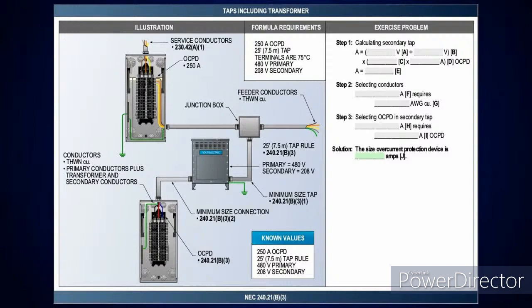All right. Absolutely. Now this one, you've got an upstream 250 amp overcurrent device that's given. In this case, we've got a 480 volt primary, 208 volt secondary. So you're going to have to get the ratio of that. Then I'm going to take that upstream overcurrent device at a third. Then I multiply that all in, get my amperage, and go size my conductors and overcurrent device. That'll be the homework next week.